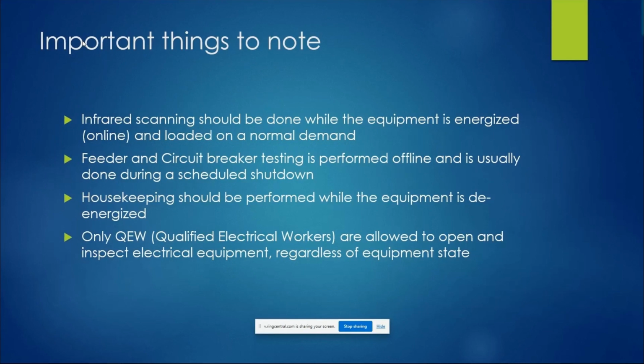In contrast to that, the feeder and circuit breaker testing is performed offline. That's usually done during your scheduled shutdowns. And then you usually have to bring in somebody. It's going to involve usually a day or two of multiple people. It should be a coordinated event. Housekeeping is done while the equipment is turned off. Do not do housekeeping on any equipment while it's open and running, if possible.